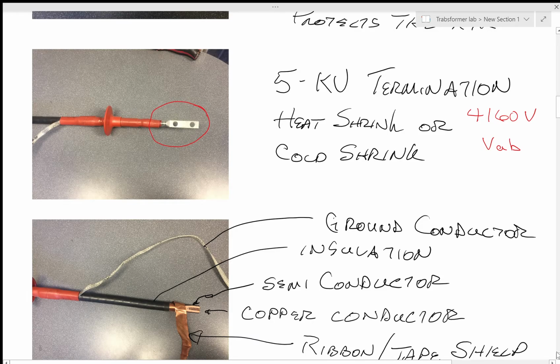These things are either shrink wrapped. You pull out this plastic spring and it collapses onto the cable, kind of like heat shrink, and insulates everything, but it's called cold shrink. And then you also have heat shrink ones. So I don't know what this one is. It's probably a cold shrink. Problem with heat shrink is if you burn that insulation, you got to strip it off and completely put a new one on there. This is a different type of cable.